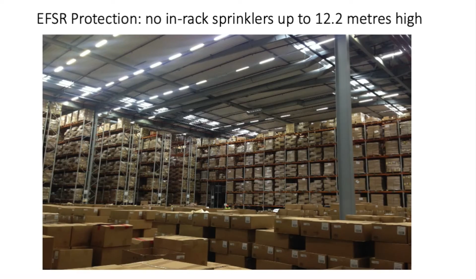So then we come to water supplies. So warehouses should have a minimum of a superior single supply. What does that mean? A superior single supply means 2 pumps and 1 tank. And what we have to the left here, it's actually got 2 tanks in there. That's called a superior twin supply, where you've got half the capacity of the 1 tank split into 2. So each of these systems will have 2 pumps, and only one of the pumps can be electric. One has to be electric, and the others have to be diesel. Or you can just have diesel pumps, like we've got in the pictures to the left.